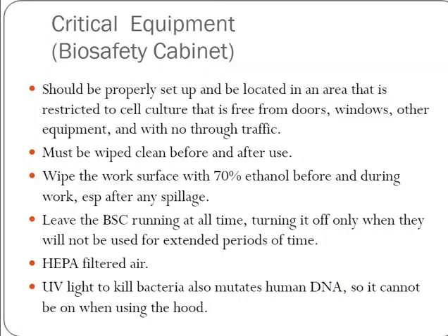Some of the critical equipment are, first of all, the biosafety cabinet. It should be properly set up and be located in an area that is restricted to cell culture, that is free from doors, windows, other equipment and with no through traffic. It must be wiped clean before and after use. The work surface has to be wiped with 70% ethanol before and during work, especially after any spillage.